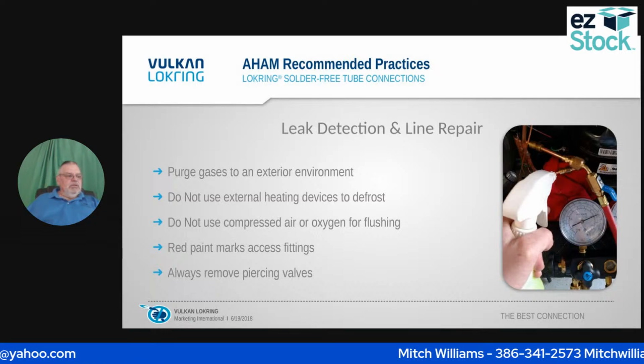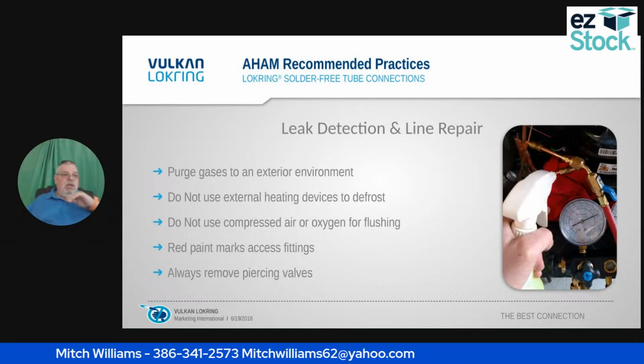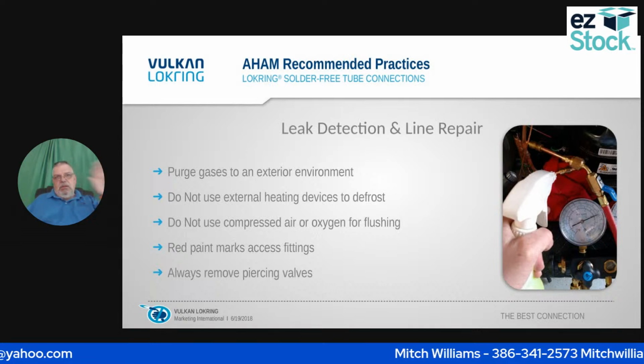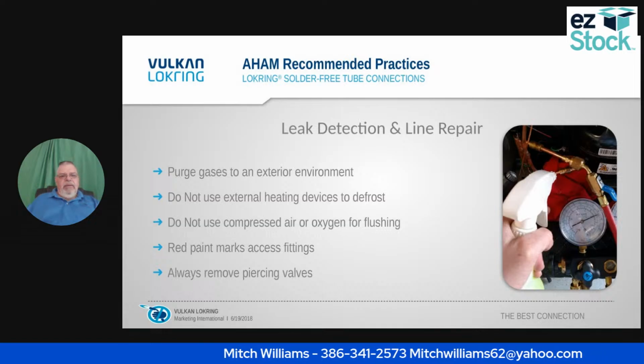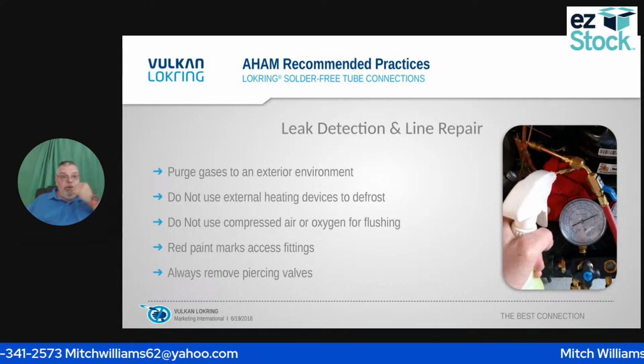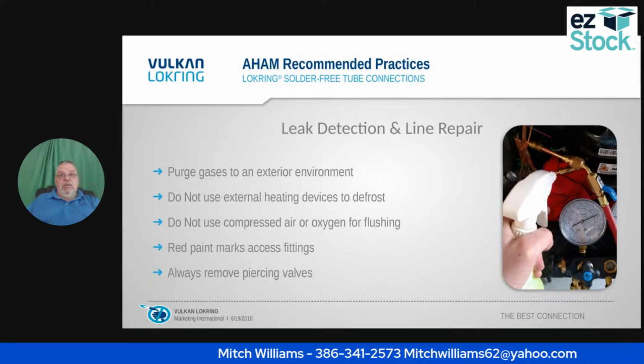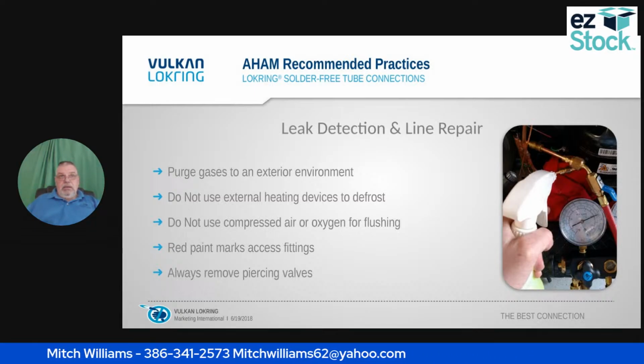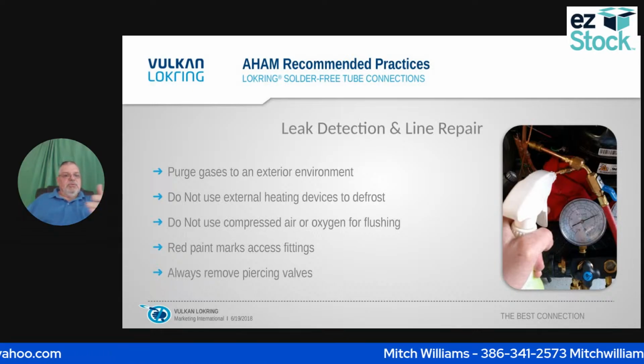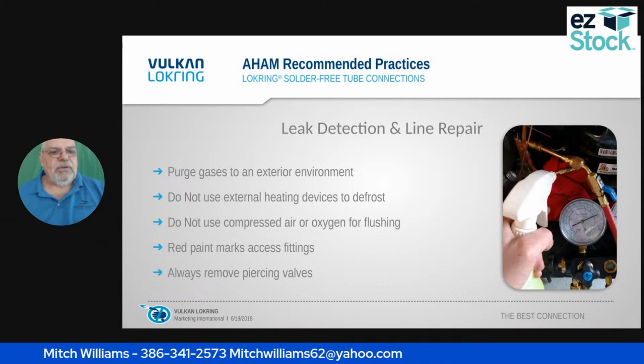As a matter of fact, Vulkan used to have, I think it was a 30-foot hose that you ran out the window. It had a little end on it, and then you put that in there, and then you just purge the gas out. Well, they had a lady that was, and again, like I said, this is not every time, but you have to remember this is a flammable refrigerant. So this lady was out there smoking and caused the ignition because of her cigarette. So just got to be super careful. That's the reason I don't purge the gas to the outside. I purge it into a bag. I'm trying to be as careful as I can.